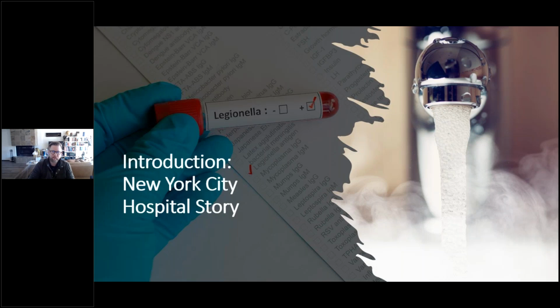As we were trying to diagnose it, one of the questions that came up was, what was the test and balance report? Was this system balanced? And when we went back and looked, sure enough, this one system had a balancing valve on it that was not balanced properly. In essence, it created a gigantic operational dead leg in this one branch that led to waterborne pathogen, specifically Legionella, growth over and over and over again, no matter how much flushing occurred. So it's worth noting that the hot water recirculation systems, the return side especially, have a big impact. And we have to think about it in terms of systems.